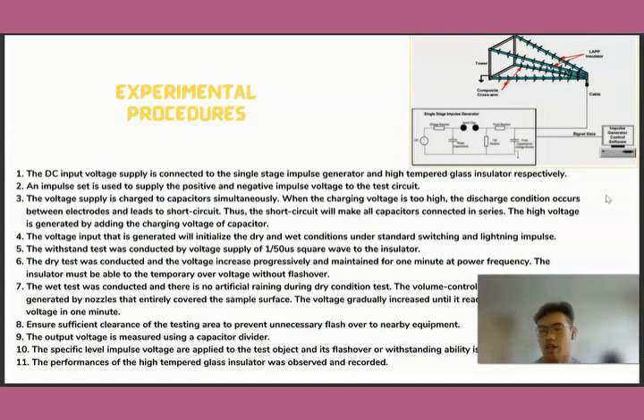Eighth, we ensure sufficient clearance of the testing area to prevent unnecessary flashover to nearby equipment. Ninth, the output voltage is measured using the capacitor divider. Tenth, the specific level impulse voltages are applied to the test object and its flashover or withstanding ability is monitored. Eleventh, the performance of the high tempered glass insulator is observed and recorded. Okay, that's all for the experimental procedure.